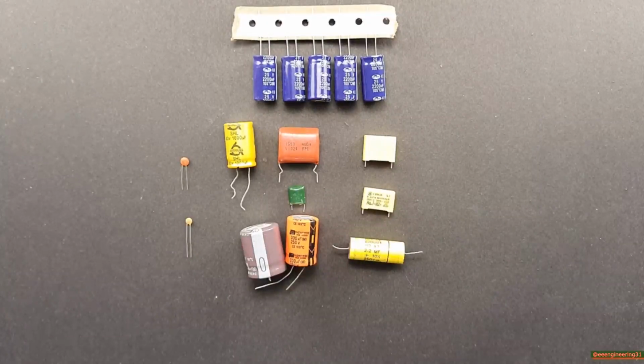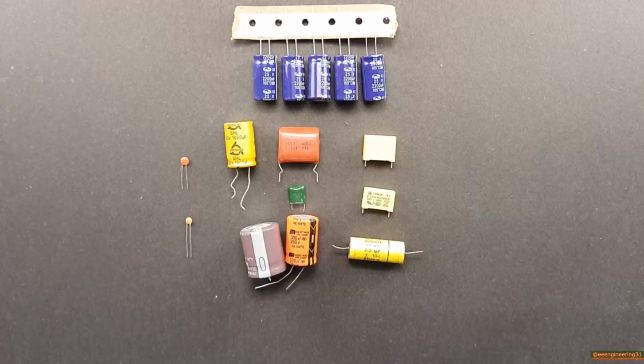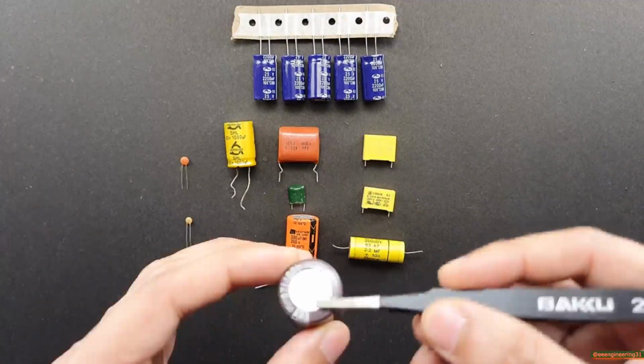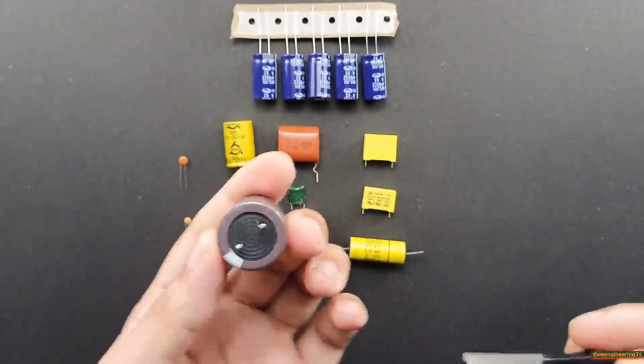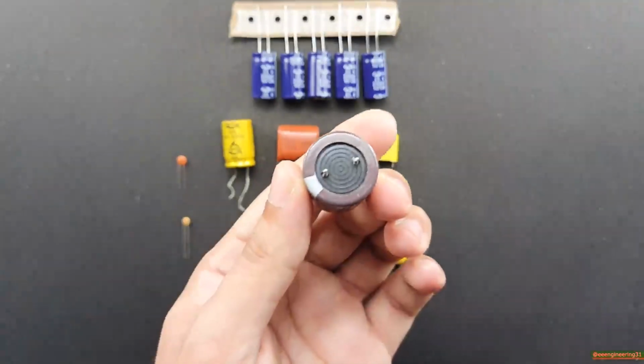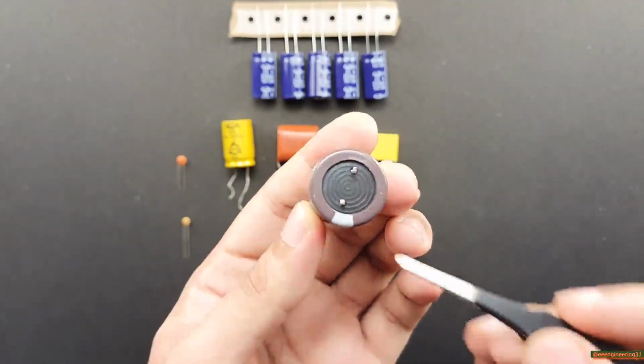Failure modes include shorts, opens, loss of capacitance from age or drying out, electrical leakage, which is essentially a partial short, and increased internal resistance, or ESR, which stands for equivalent series resistance. If you see a bulge in the top of the capacitor, or anywhere on it for that matter, it is a bad capacitor and must be replaced. Keep in mind that a capacitor can also exhibit high ESR or decreased capacitance with no physical signs. Sometimes the top portion will be bulging out, and sometimes there will be leakage at the bottom of the legs. That is a clear, obvious sign of capacitor failure.